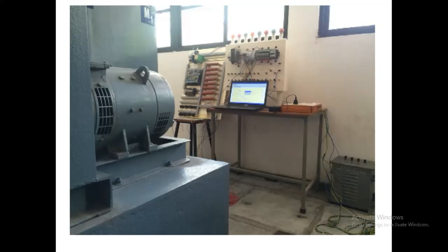This approach is based on providing a variable DC voltage to the armature circuit of a DC motor from a fixed DC supply voltage via PLC for supply voltage control method. A relay-based PLC control method is used for switching on or off the resistor which can connect it in series with the armature and field circuit of a DC motor depending on the reference speed for armature and field control method.